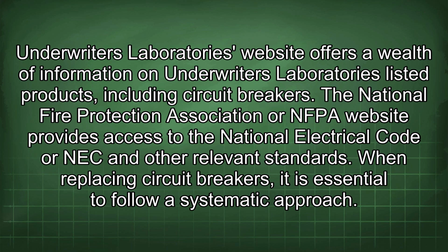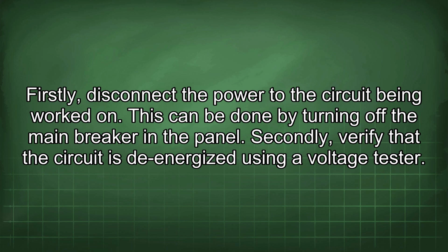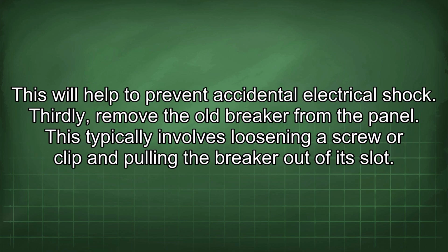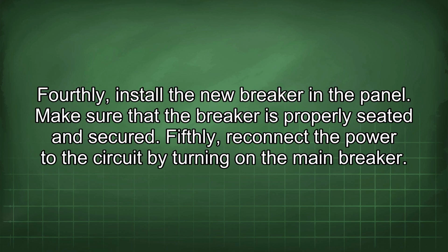standards. When replacing circuit breakers, it is essential to follow a systematic approach. Firstly, disconnect the power to the circuit being worked on. This can be done by turning off the main breaker in the panel. Secondly, verify that the circuit is de-energized using a voltage tester. This will help to prevent accidental electrical shock. Thirdly, remove the old breaker from the panel. This typically involves loosening a screw or clip and pulling the breaker out of its slot. Fourthly, install the new breaker in the panel. Make sure that the breaker is properly seated and secured.